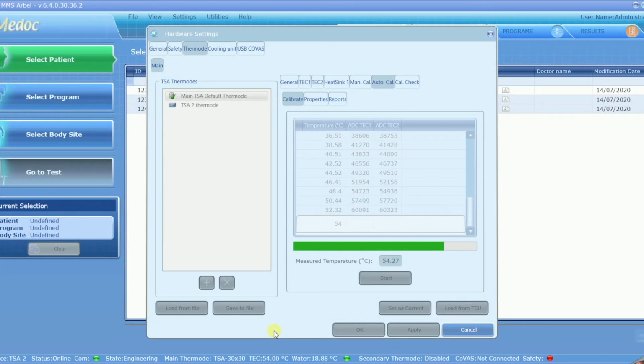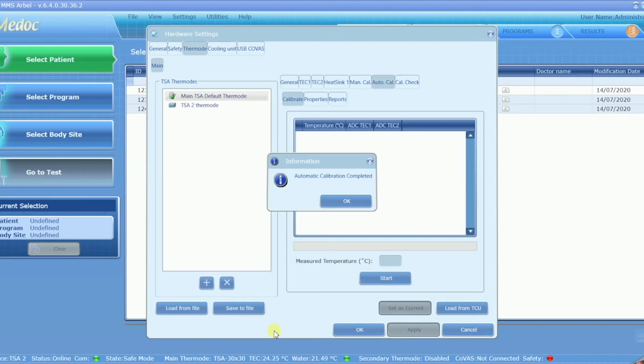So this is the last point that you see over here, the 54 degrees, the last point of the temperature range that is tested. In a second we'll see that everything will stop, and we'll get a signal that the auto calibration has been ended. We'll just wait for the green bar to fill up. It's showing all the temperature points that have been tested. And the auto calibration has been completed. We'll press OK.